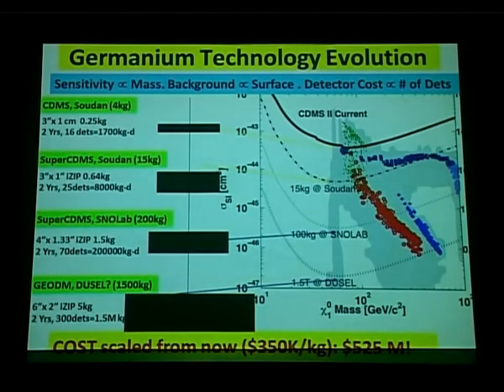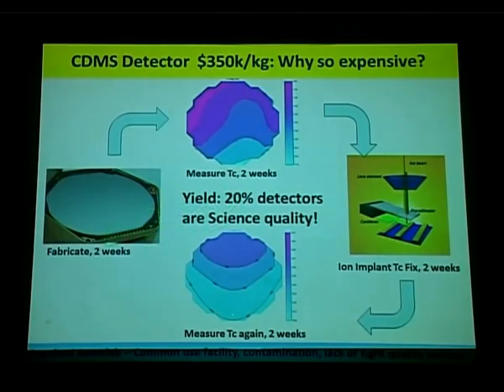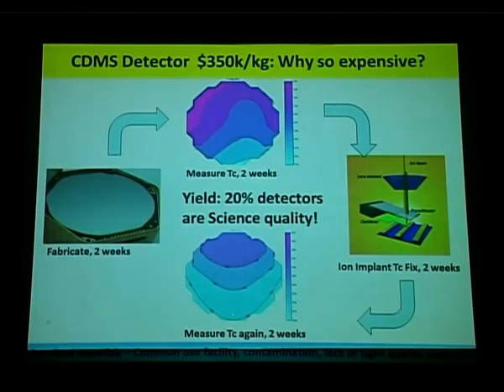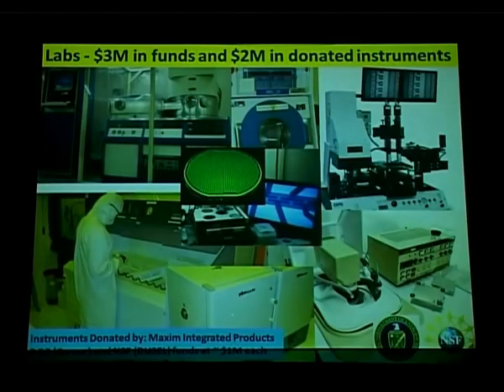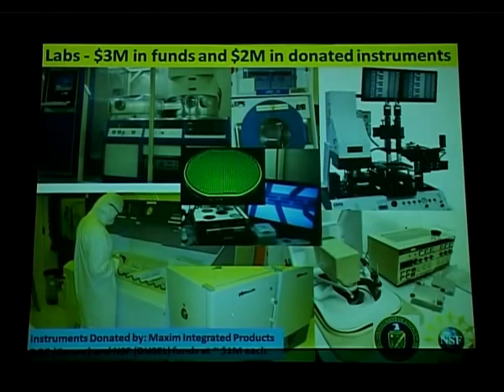So we attacked the problem of where the inefficiencies come from. Detectors used to be made exclusively at Stanford, taking two weeks per detector in a common nanofabrication facility, with TC uniformity problems requiring ion implantation fixes — each detector taking about two months, and only one in five succeeding. So we decided to industrialize. We set up a lab at Texas A&M with external funding and donated instruments from the semiconductor industry. With industrial quality instruments, you have a higher success rate, which drives down cost.